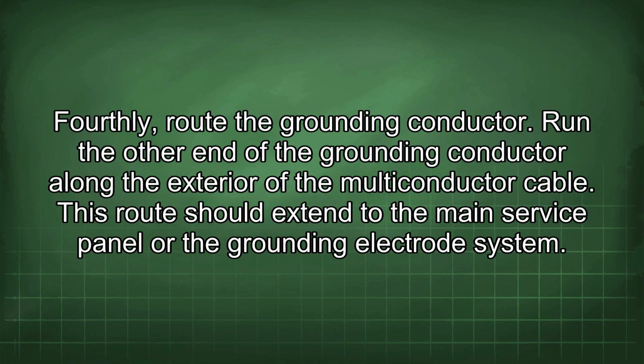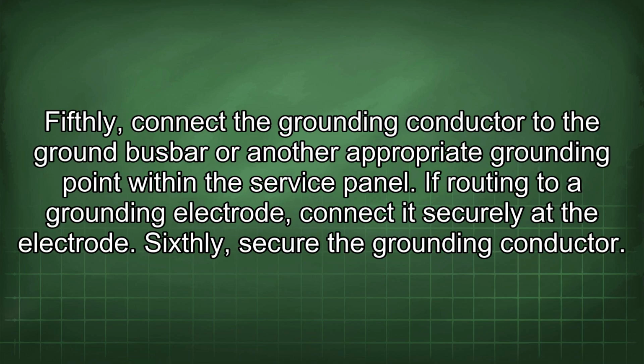Fourthly, route the grounding conductor. Run the other end of the grounding conductor along the exterior of the multiconductor cable. This route should extend to the main service panel or the grounding electrode system. Fifthly, connect the grounding conductor to the ground busbar or another appropriate grounding point within the service panel. If routing to a grounding electrode, connect it securely at the electrode.